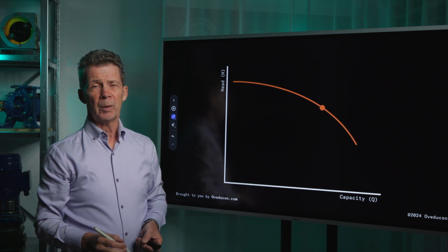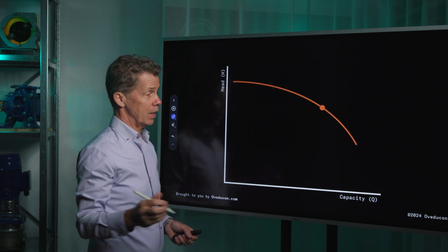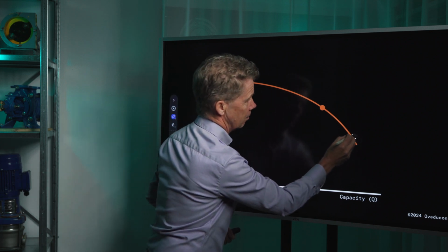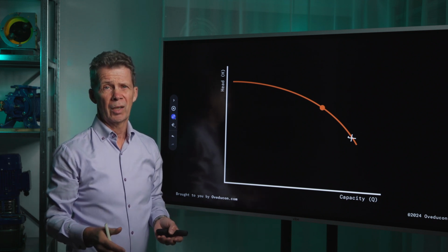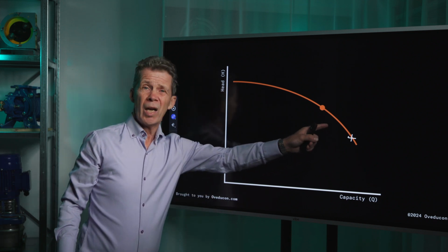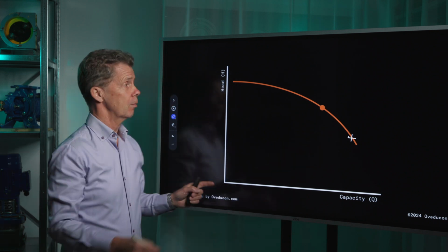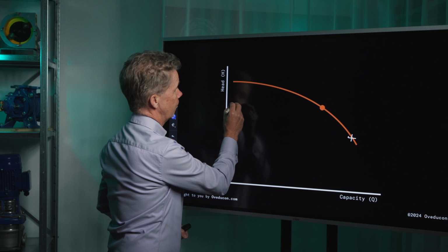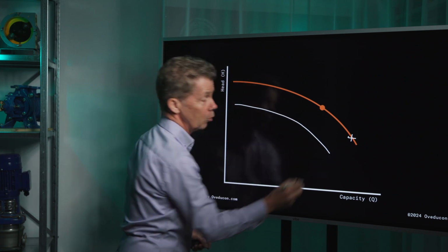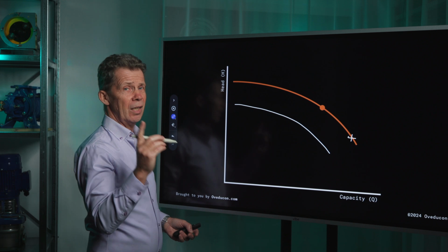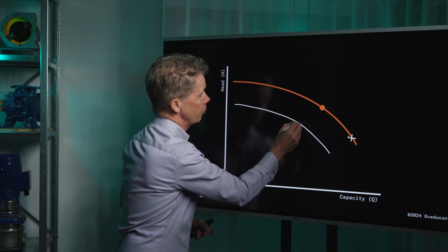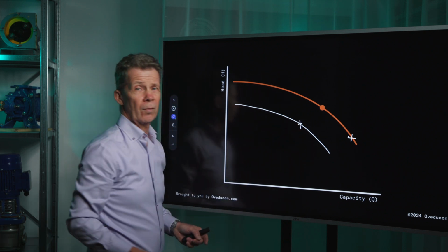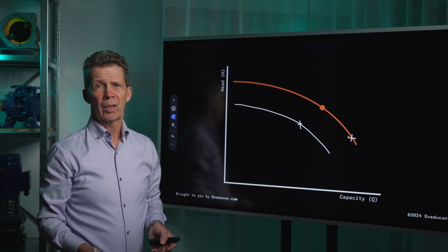Now there are a lot of people who think that if you have a bad pump sizing, like at this point, which will be the operating point in this example, and you have a low reliability, then we use a frequency drive. So this will be the pump curve with a frequency drive, and they think that the operating point will go to another point, for example here. A much better point. But is this really what will happen?